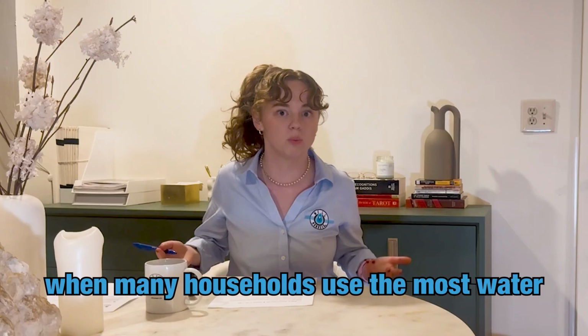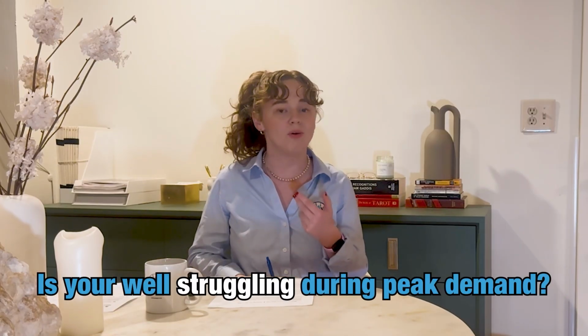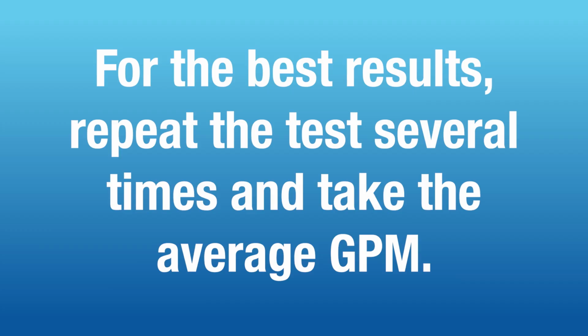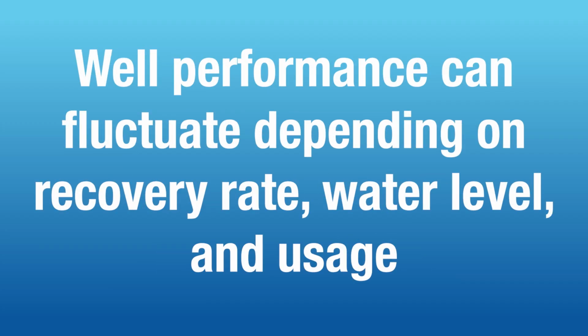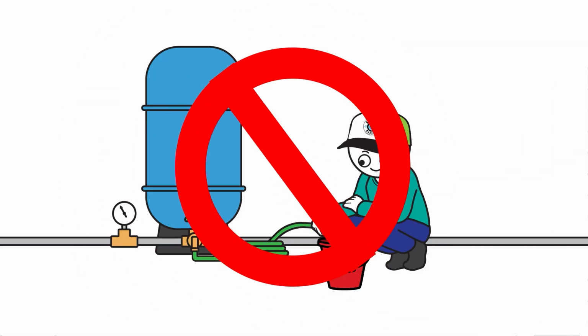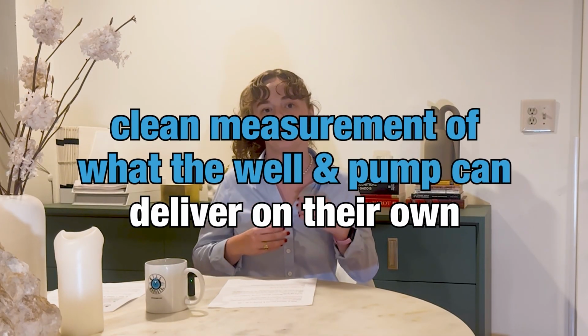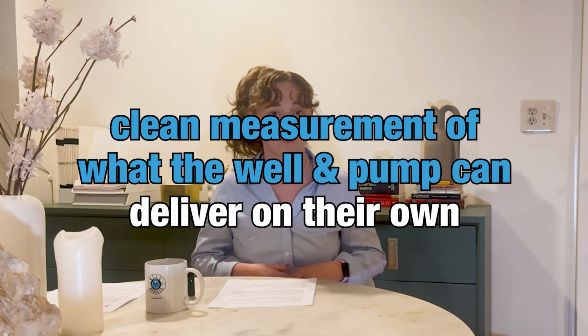Write down both results and the time of day that you tested. Now, we usually recommend testing during the morning or the evening, which is when many households use the most water. That way you can see if your well really is struggling during a peak demand. We do want to avoid running this test when anyone else is using water in the house. That will disrupt the test, not give you a clean answer. You want a clean measurement of what the well and the pump can deliver on their own.